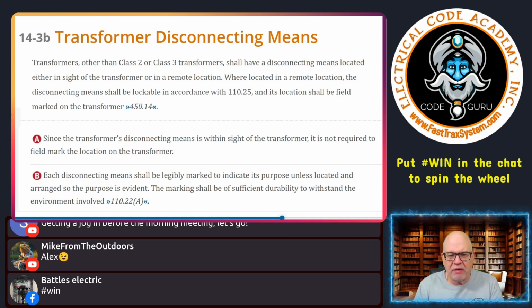And remember, what we're talking about is the protection for the transformer. Now, it may or may not provide adequate protection for the conductors, the primary side, or even the secondary side. So we have to consciously think about that when we're protecting the transformer. We're going to be talking disconnecting means today, though, first. But talking about overcurrent protection, it does us no good to protect the transformers on the primary side if it doesn't also protect the primary conductors, and in many cases, even the secondary conductors. So all those things are extremely important when you're dealing with transformers.